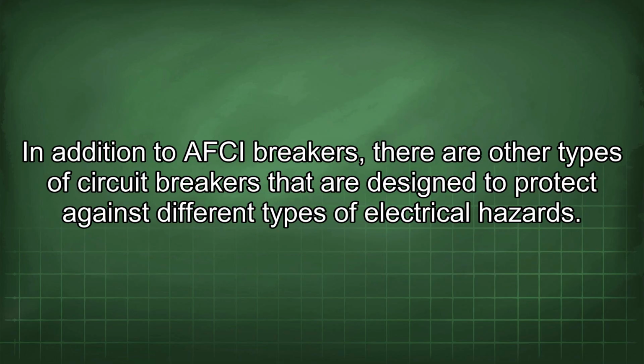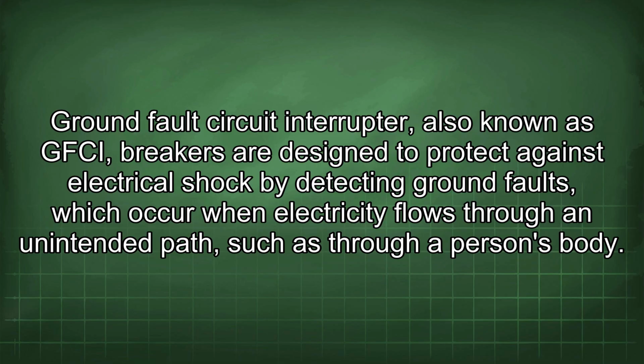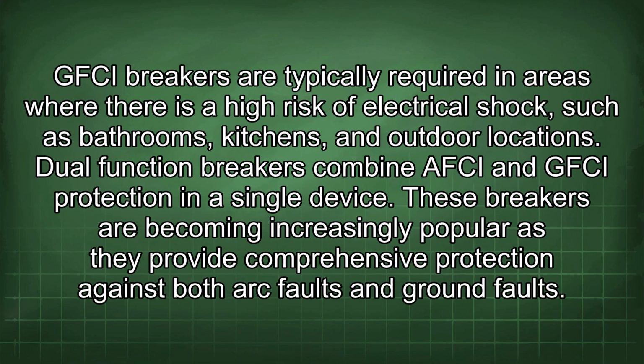In addition to AFCI breakers, there are other types of circuit breakers that are designed to protect against different types of electrical hazards. Ground fault circuit interrupter, also known as GFCI, breakers are designed to protect against electrical shock by detecting ground faults, which occur when electricity flows through an unintended path, such as through a person's body. GFCI breakers are typically required in areas where there is a high risk of electrical shock, such as bathrooms, kitchens, and outdoor locations. Dual-function breakers combine AFCI and GFCI protection in a single device. These breakers are becoming increasingly popular as they provide comprehensive protection against both arc faults and ground faults.